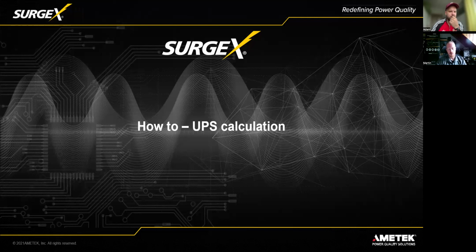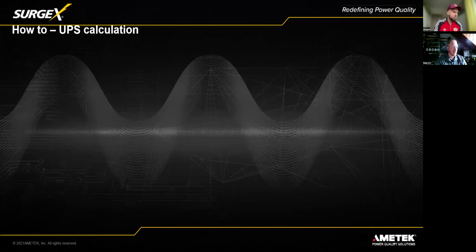What we mostly recognize is that UPSs are too small. Customers come back to us and ask, when they have 2,000 watts of load, for a 2 kVA unit, and that wouldn't work. Then the batteries only run for 2-3 minutes before switching off. So I wanted to help you understand which UPS to choose and how to size it for the load.